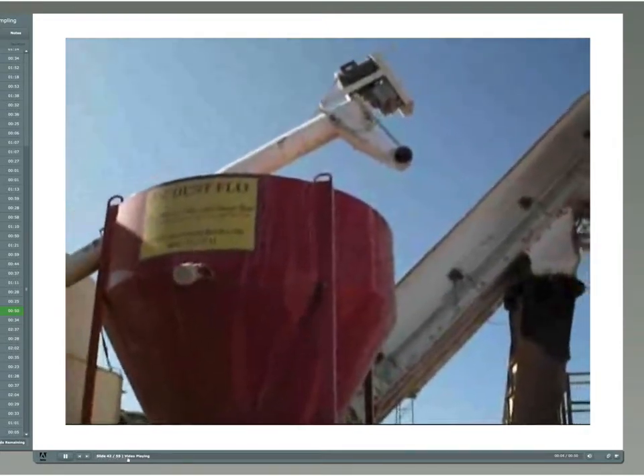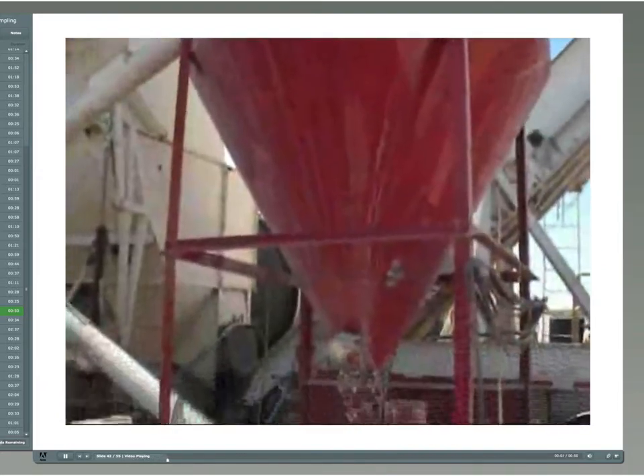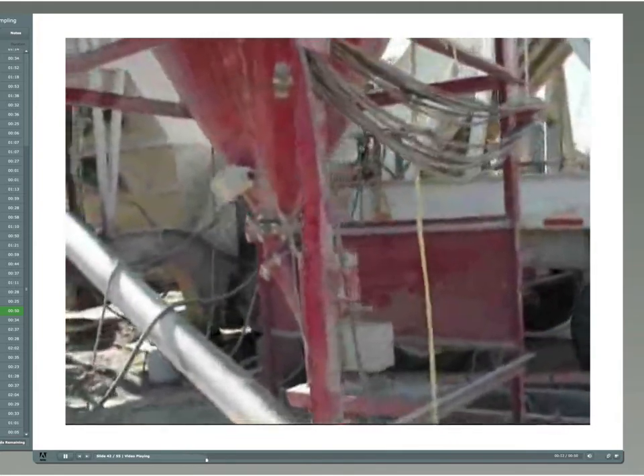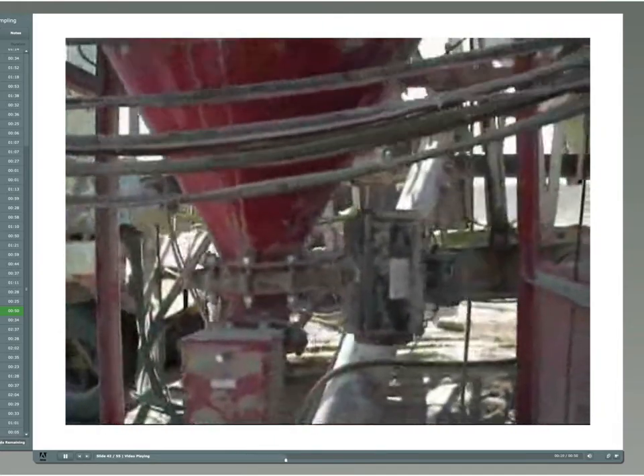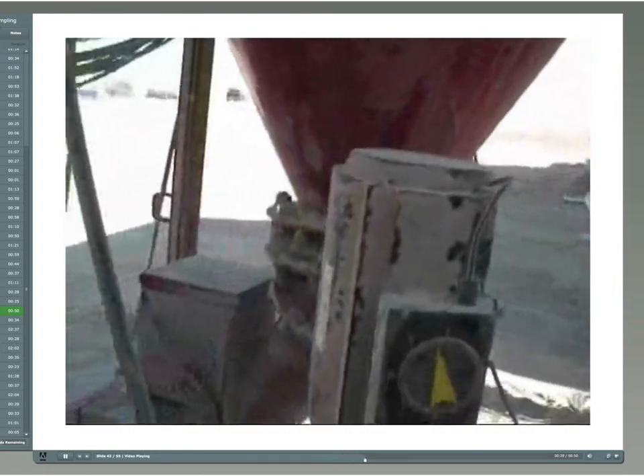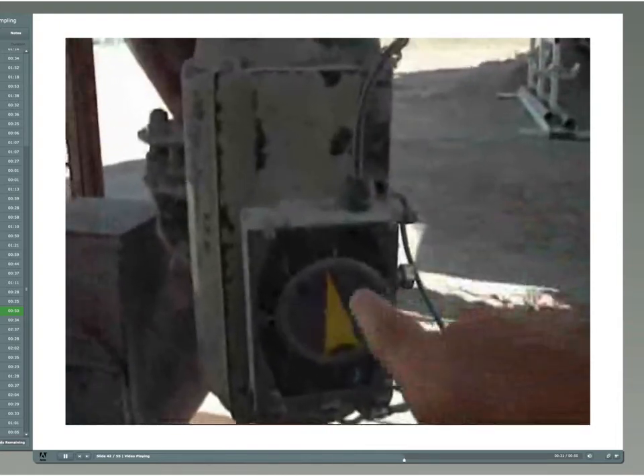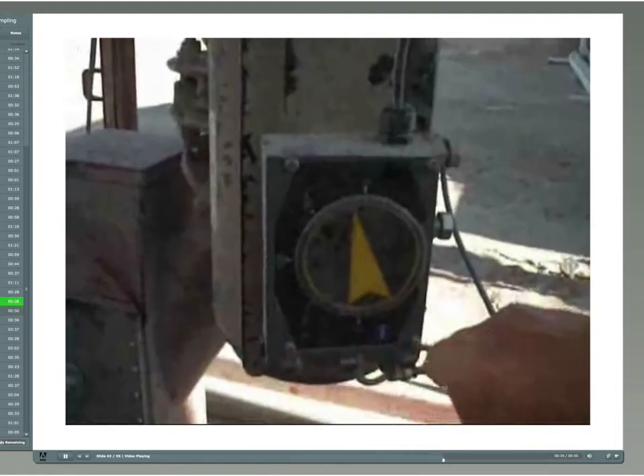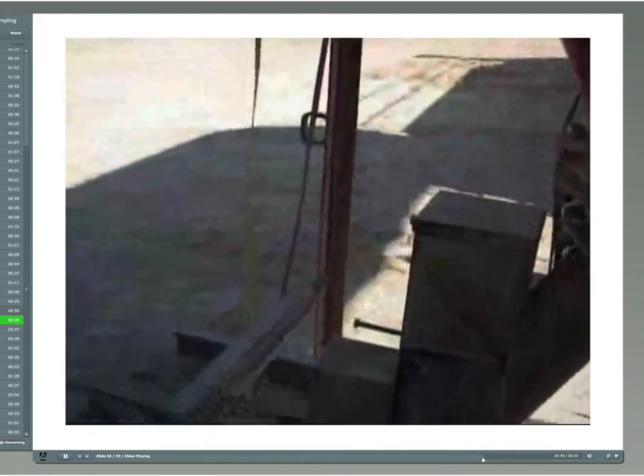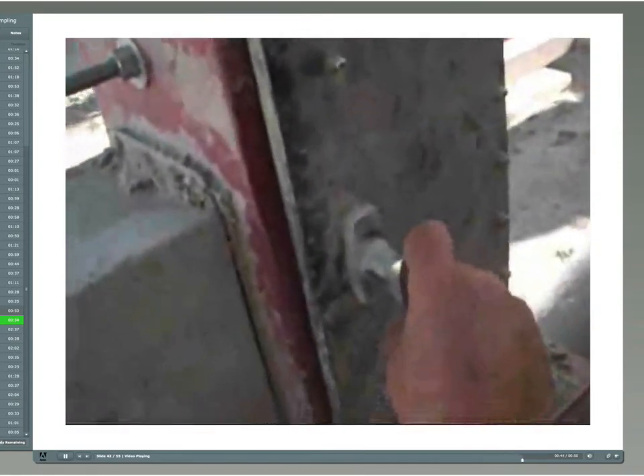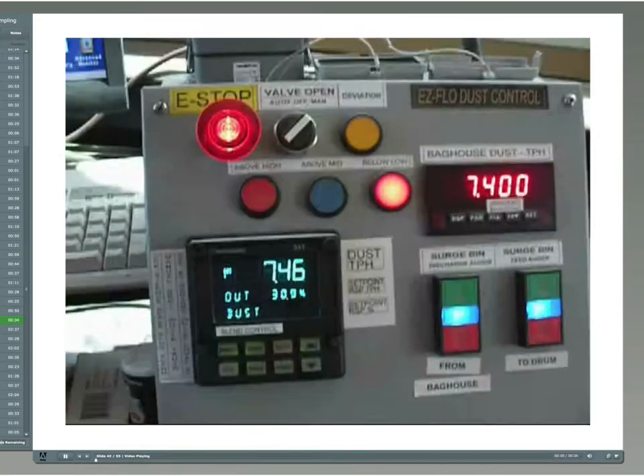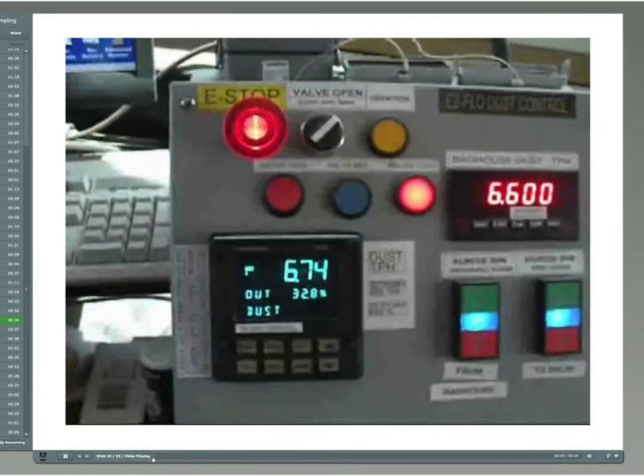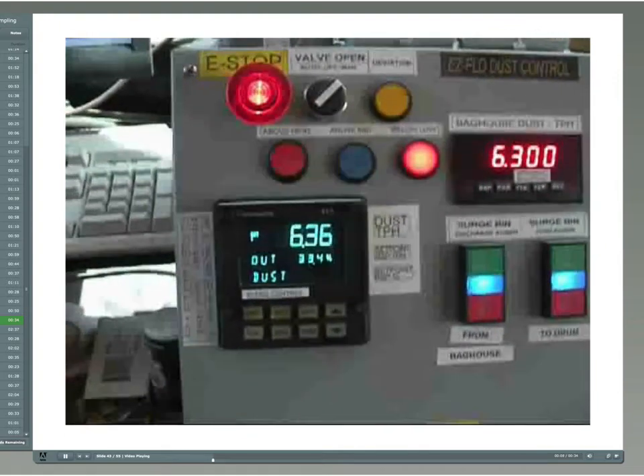Controlling various processes is usually simple when the variables are predictable and consistent. The measuring device is right next to the flow control device, meaning there is hardly any delay from the time the flow control valve is adjusted and the flow rate is measured. This allows for a very smooth and tight control with little or no hunting when material is delivered to the flow control valve consistently.